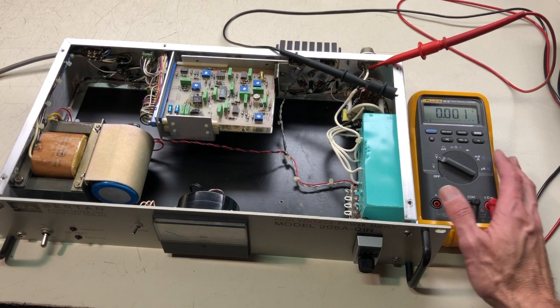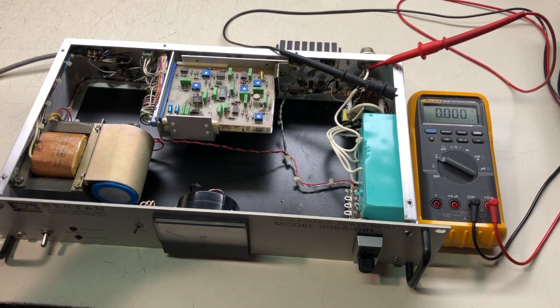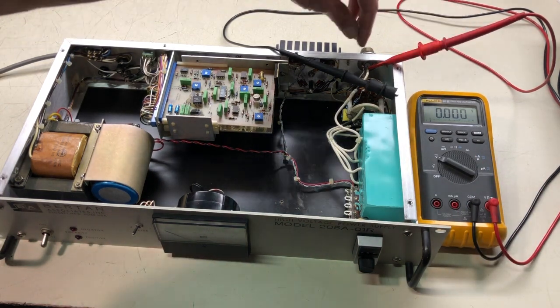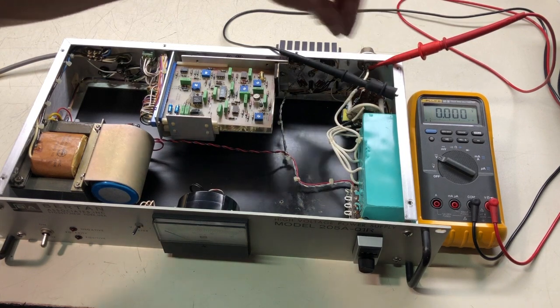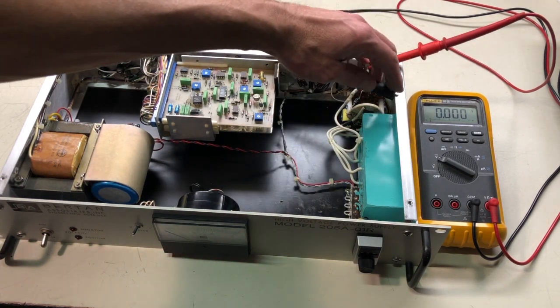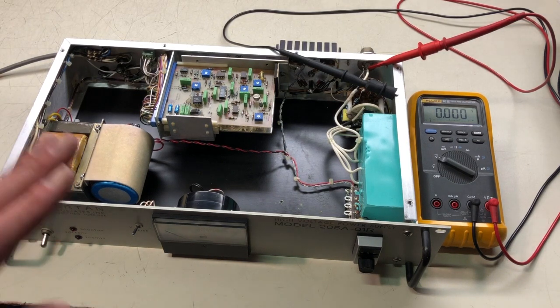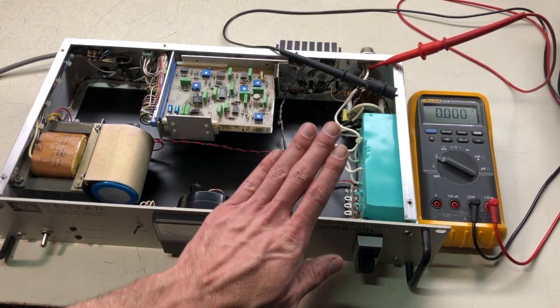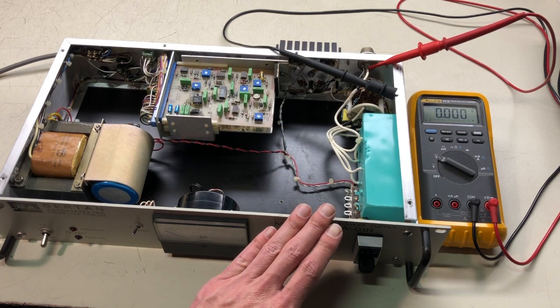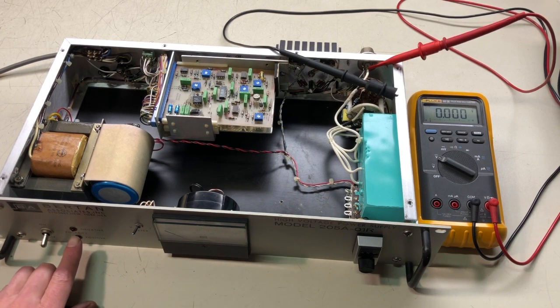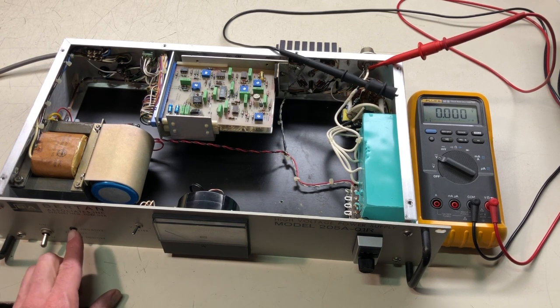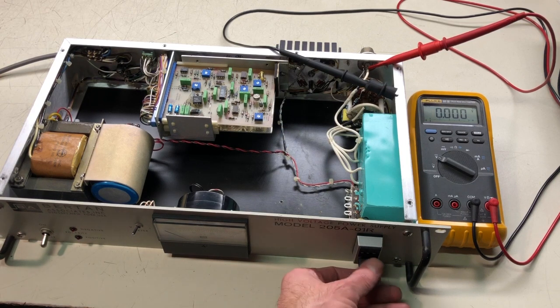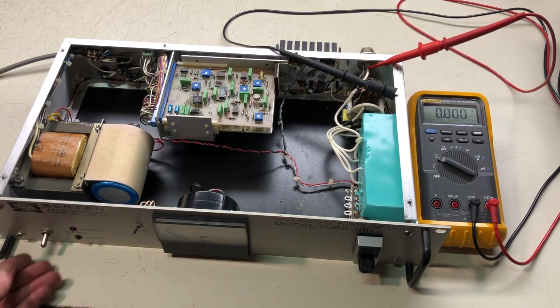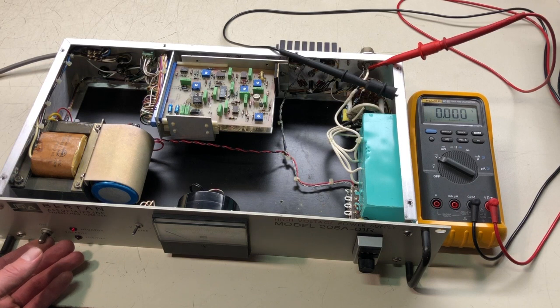Okay, I have the meter set up to measure DC voltage. The positive lead is connected to the high voltage output, and the negative lead is just on chassis ground. Now the rear panel output polarity switch has been changed over to the negative position. So on the front panel, over here we have the negative positive polarity, and it's been on positive. We'll look for the negative LED to turn on. So voltage is set to 0. Voltmeter position, so go ahead and turn that on.